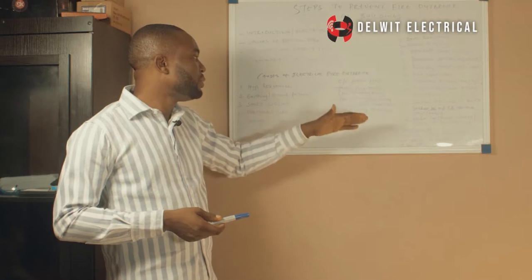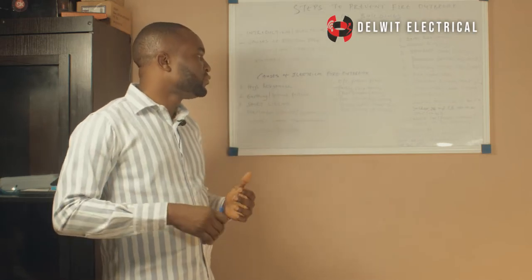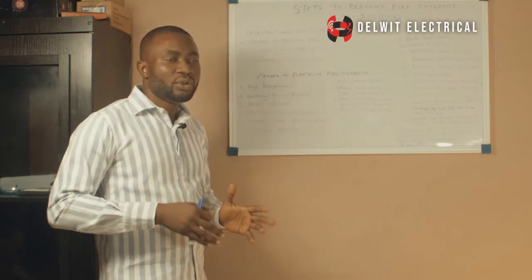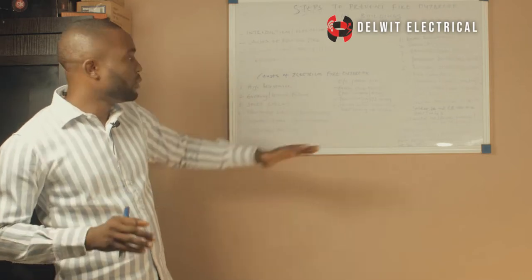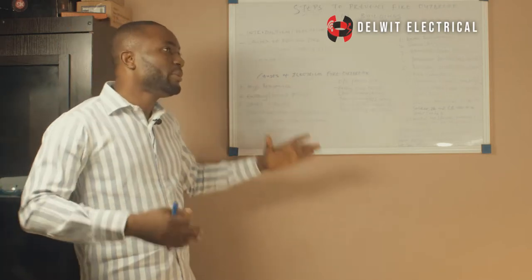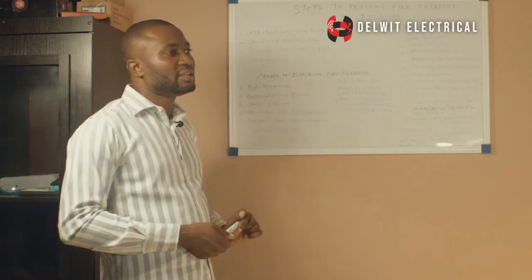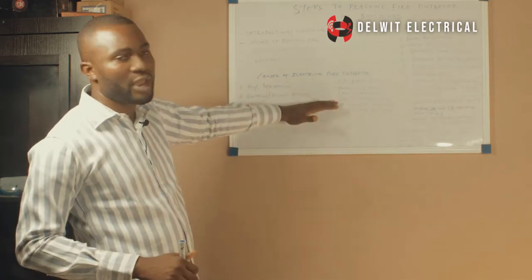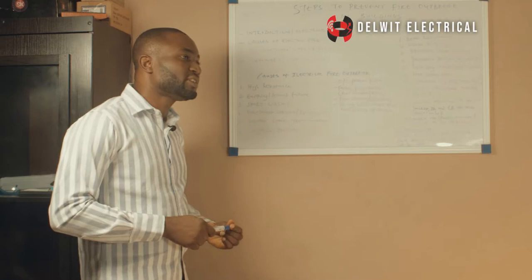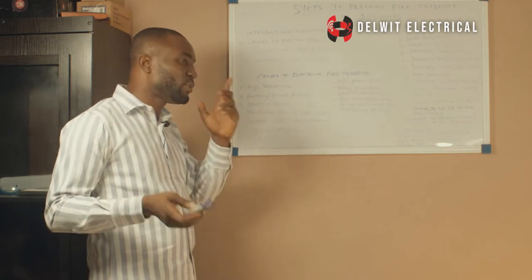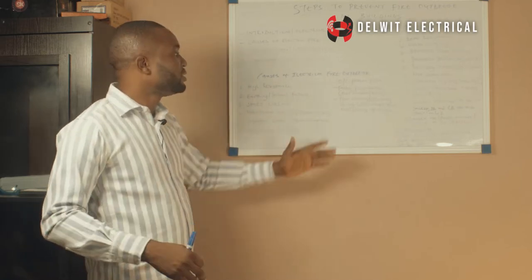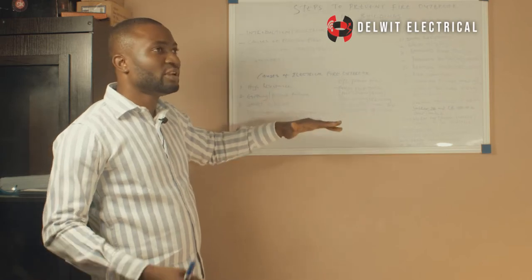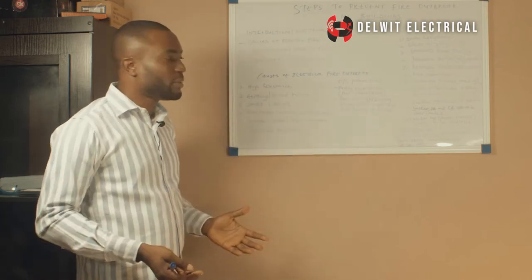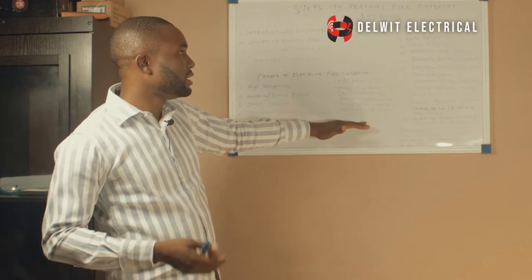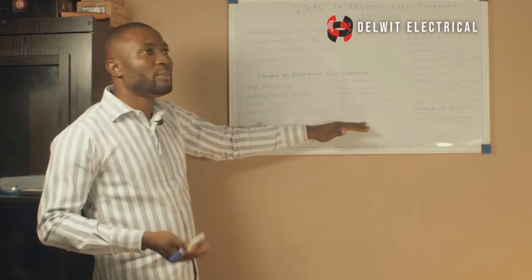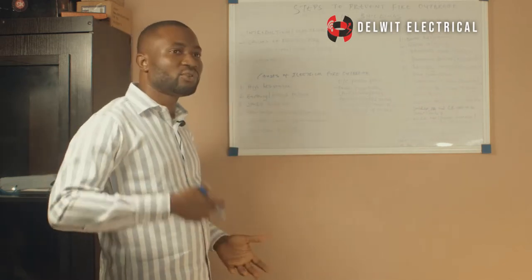Now, wiring below rated standard, or rated load. Every load has its own rating, which is covered in the electrical design. So maybe the electrical engineer has designed that for your AC point, you are supposed to use 4 mm. You tell me that, I'm an electrician, for the past 20 years I've been wiring buildings and I've been using 2.5. You use 2.5, and because in their own time they didn't have constant power supply, you put on your AC at 8 a.m., 12 noon, by 3 p.m. you have put it off. The wire is not used continuously.